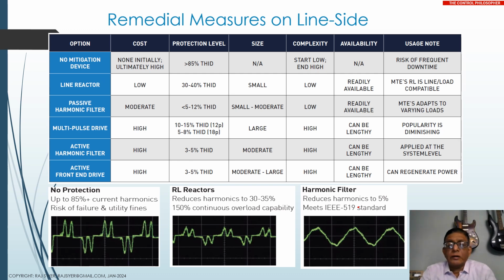And if you add a little filter and output choke and things like that, output chokes are not really required if you have less than 50-meter cable distance to the motor. Okay, this is only a brief summary. Now you have to go by the manufacturer recommendation and study to what extent the drive itself is managing the harmonics. Very often people like Siemens, Yaskawa, Schneider say that this is the rating of the line filter, the choke. They give you some formula to calculate. But yes, this is how you mitigate the influence of harmonics.